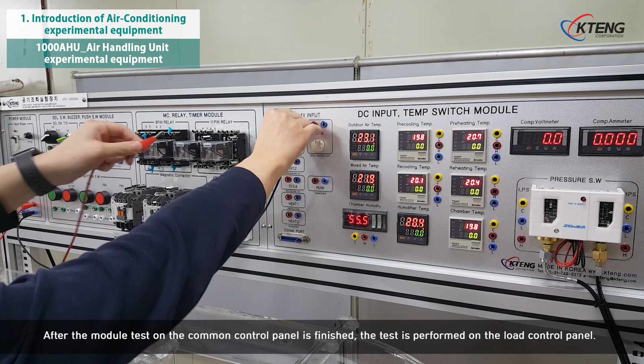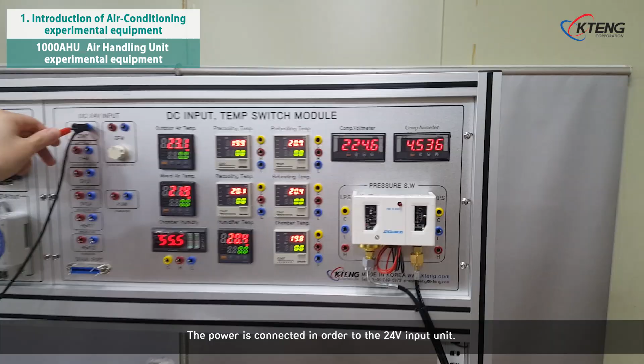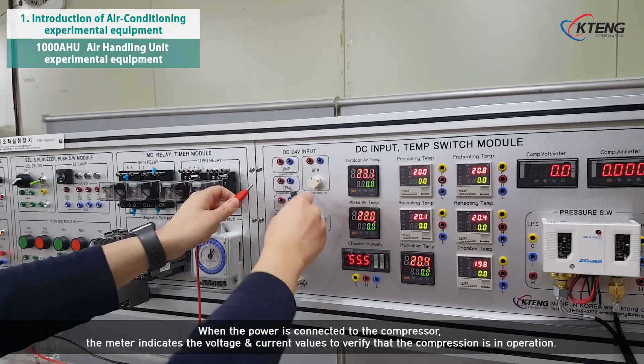After the module test on the common control panel is finished, the test is performed on the load control panel. The power is connected in order to the 24-volt input unit. When the power is connected to the compressor, the meter indicates the voltage and current values to verify that the compressor is in operation. Then, the power is connected to the condenser to check whether the condenser fan is rotating properly.